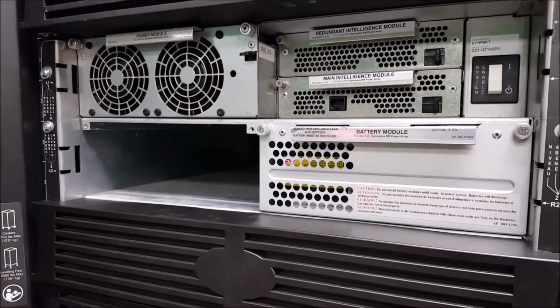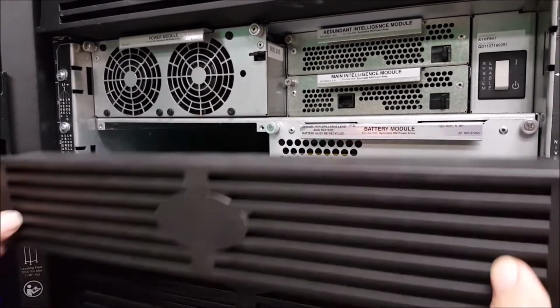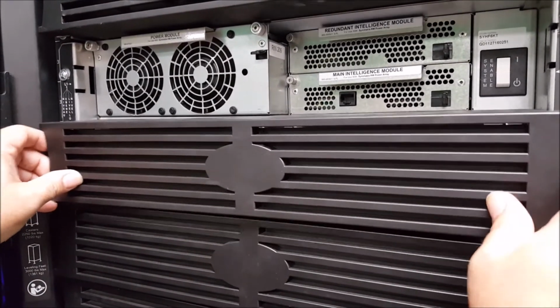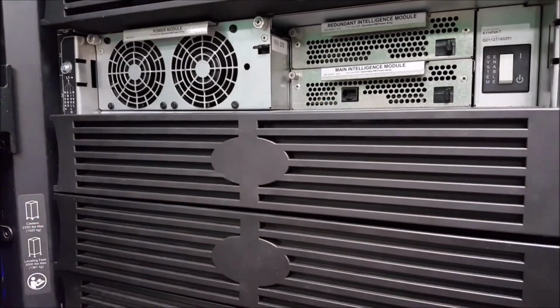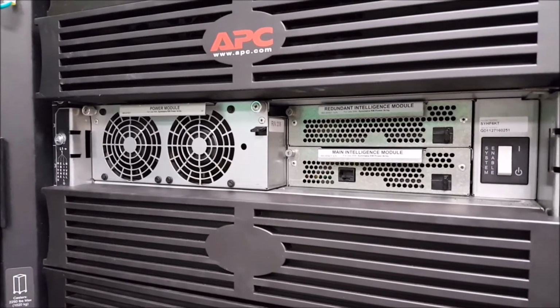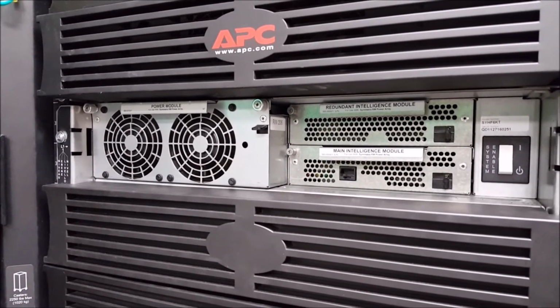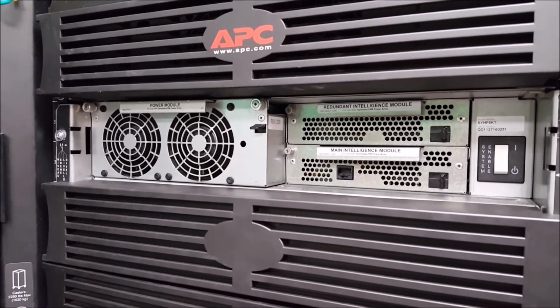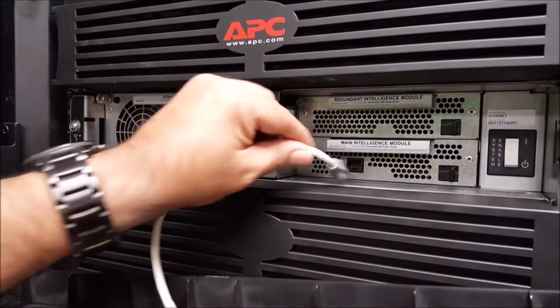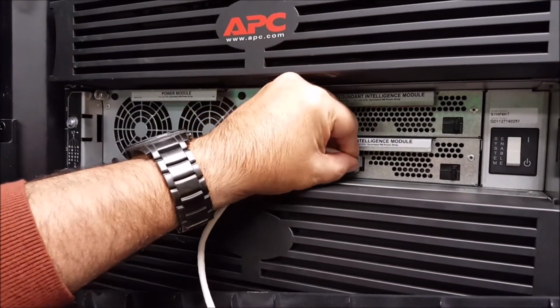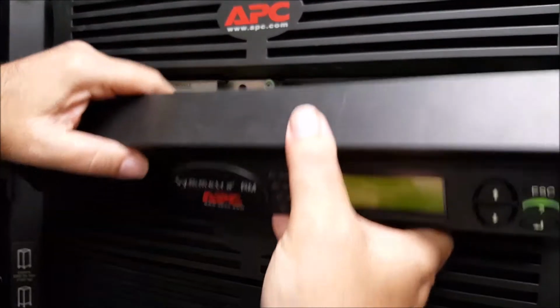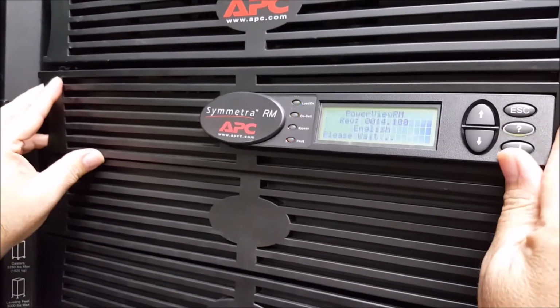Now that the UPS has been powered back on again, you'll want to reattach the bezel covers to the front of the unit. When reattaching the front bezel that holds the power view display into the Symmetra RM unit, please be sure to plug the Ethernet cable into the RJ45 port on the main intelligence module. If done correctly, you will see the power view display begin to boot up.